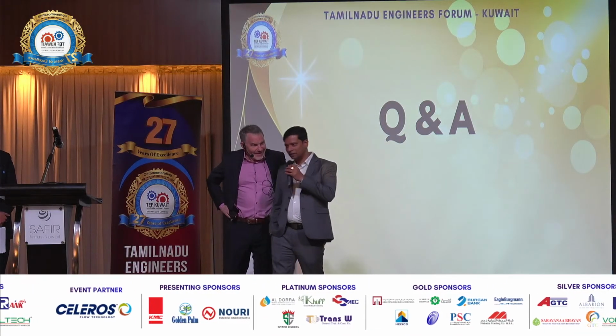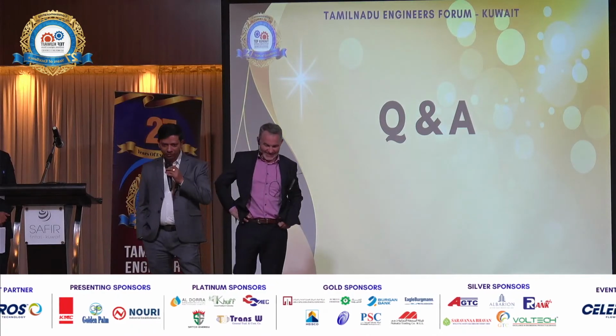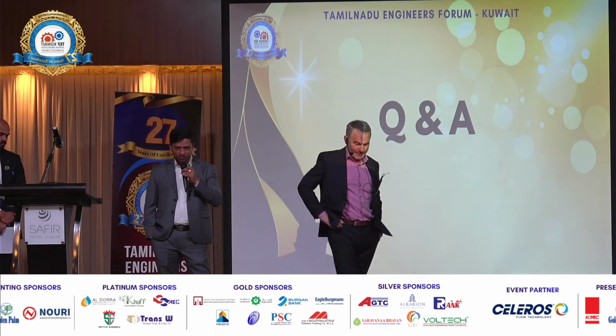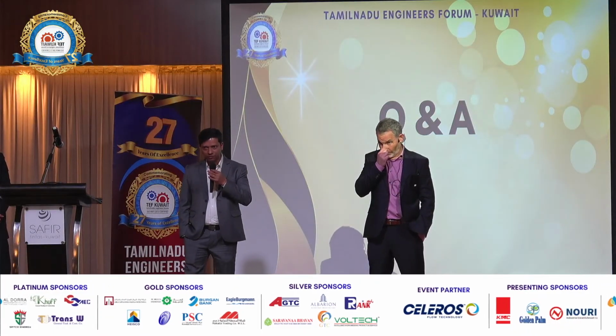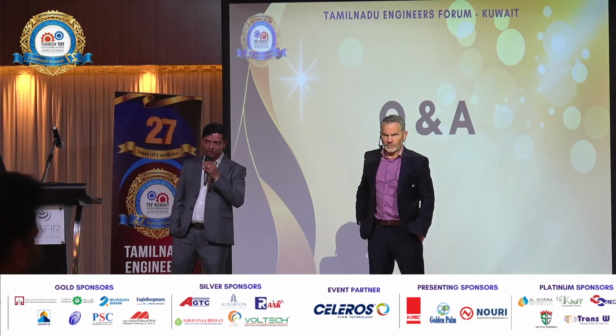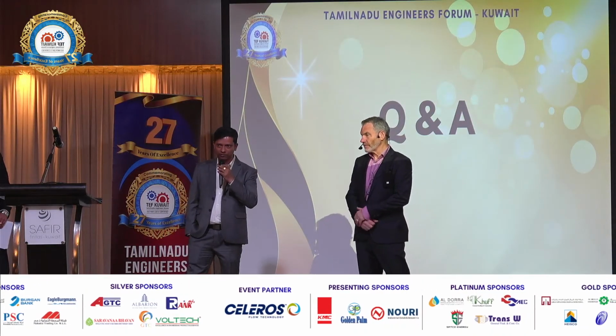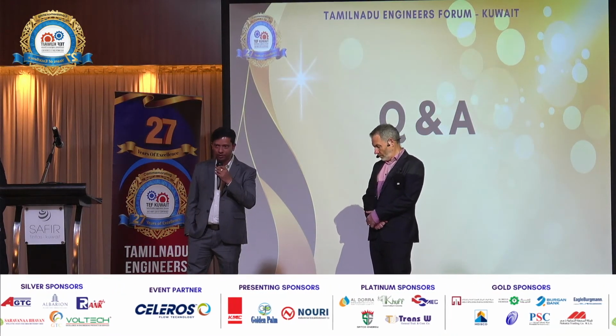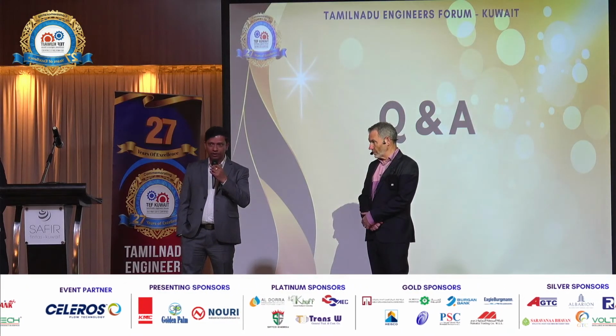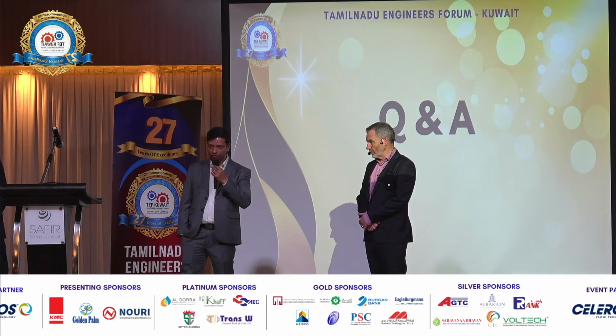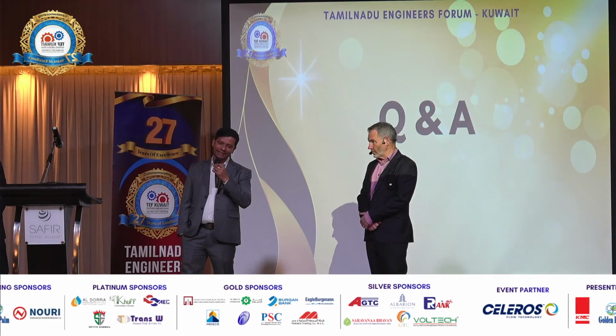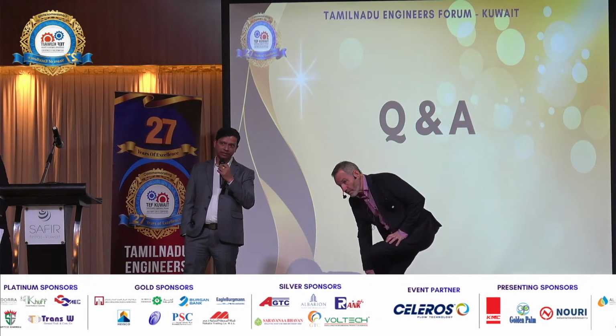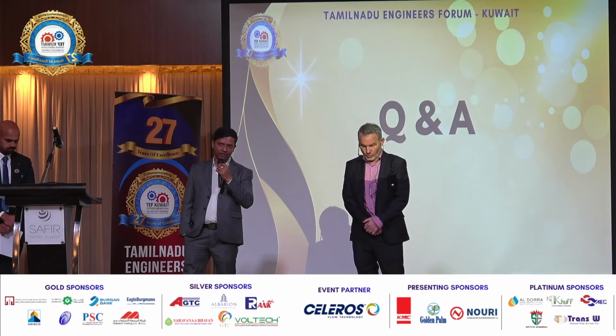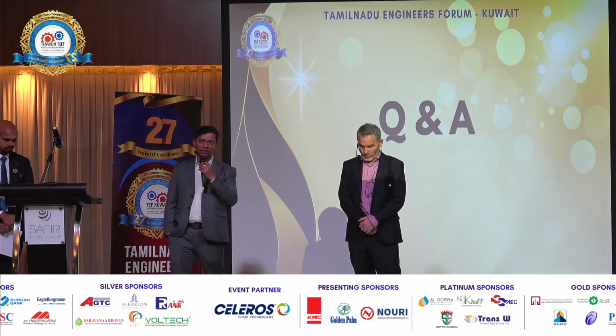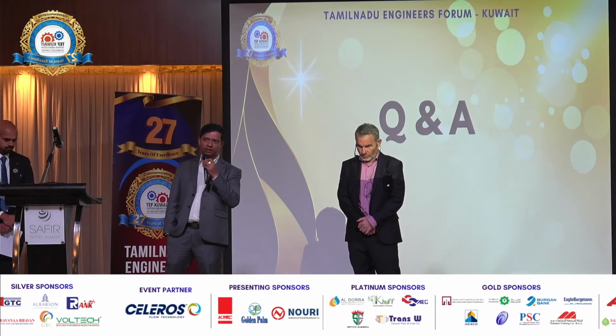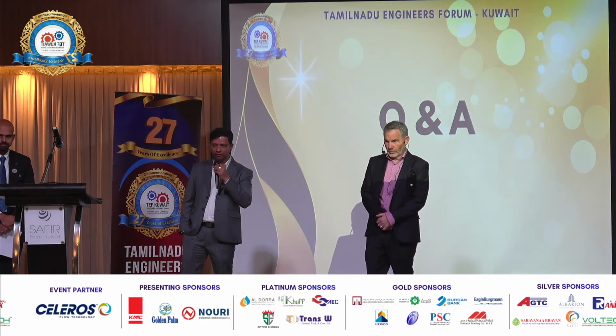Yeah, Sanjit can answer that. It depends what type of pump we are talking about, single stage or multi-stage. If it is a multi-stage pump, then we need to check the hydraulics available at that particular duty point. If you are looking for a reduction of flow, changing the hydraulics is one solution. Destaging is mainly done if there is a reduction of pressure; flow doesn't change much on that. But changing hydraulics or trimming down the existing impeller can give a solution for the reduction of the flow.